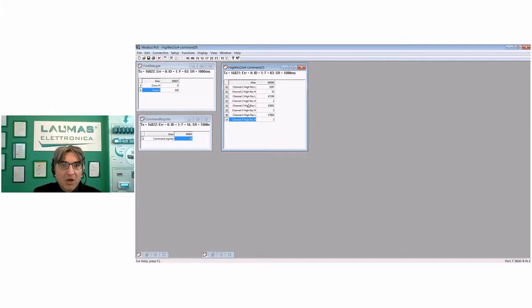So now we see only 4 channels from 1 to 4, but every channel is in its full 24-bit resolution. And now every channel takes 2 Modbus registers. So in total 32 bits. In this case, the 8 most significant bits are not used because the values are 24 bits. So here we have the channels from 1 to 4.